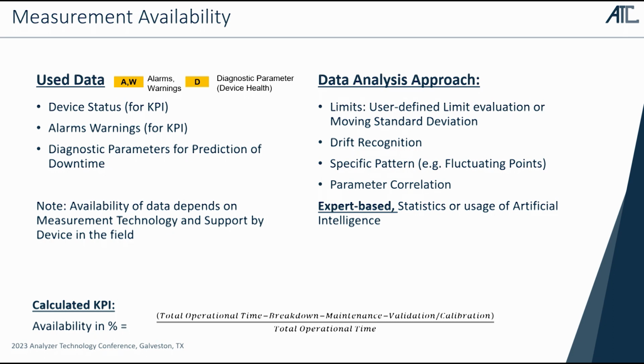What we are doing as an approach, and I have experienced this with my team in the last couple of years, is that there's a specific way to use and analyze this data, because it's not about monitoring. If you start to monitor every diagnostic parameter you have in your analyzer, you suddenly have 3,000 parameters somewhere in the software. No technician will ever read them out. It's far too much. So it's about how to use this data intelligently. That's the way to do it, because you don't have the time to look at the software every day, every minute.